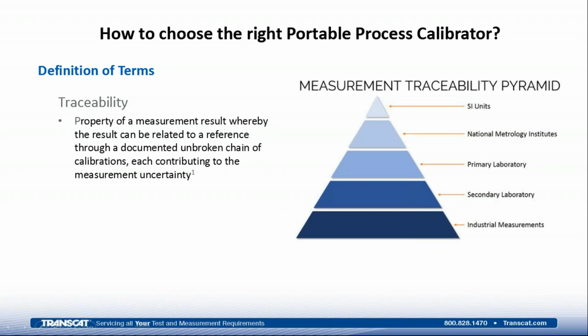Traceability. It's important to understand traceability and what that term means. It's the property of a measurement result whereby the result can be related to a reference through a documented unbroken chain of calibrations, each contributing to the measurement uncertainty. So we're usually talking about, in this pyramid of traceability that goes up to the international system of units, we're down in the industrial measurements. So our measurement devices, transfer standards and calibrators that we're using in the field are typically at the bottom of the hierarchy or pyramid of traceability.